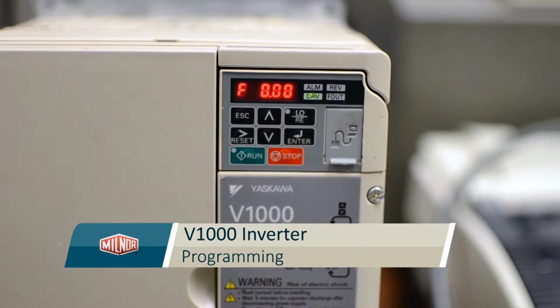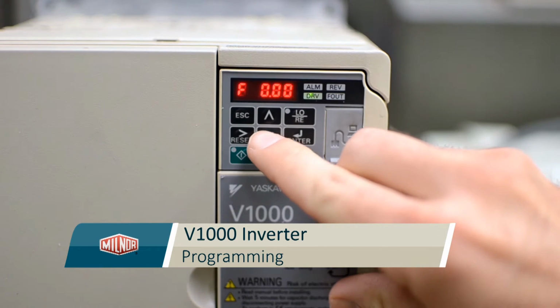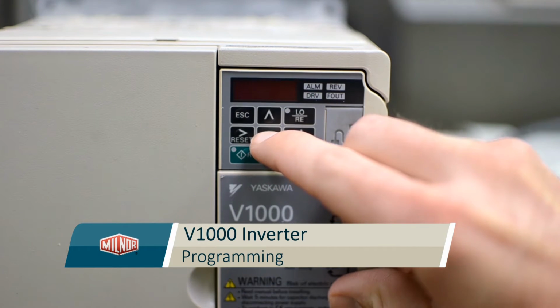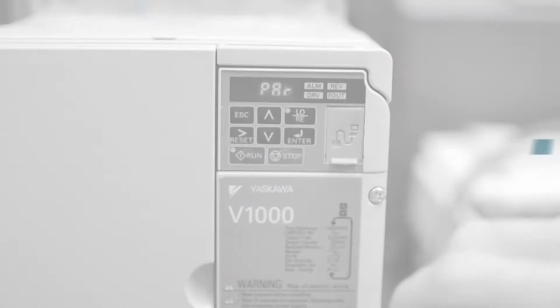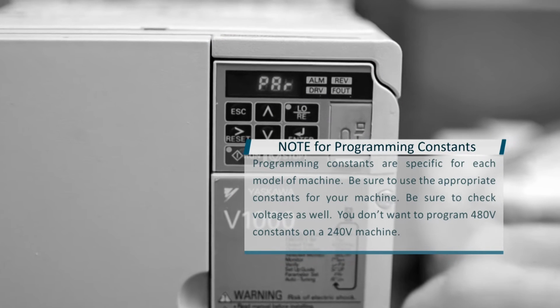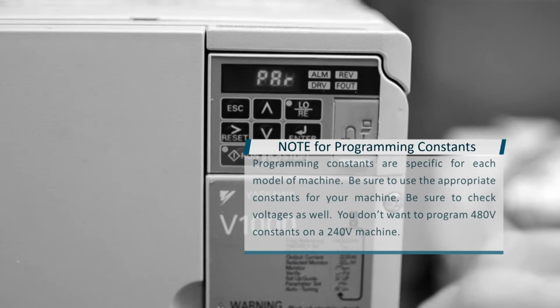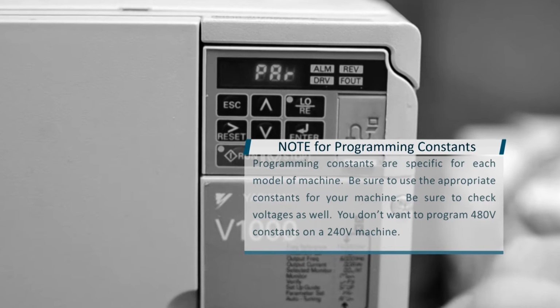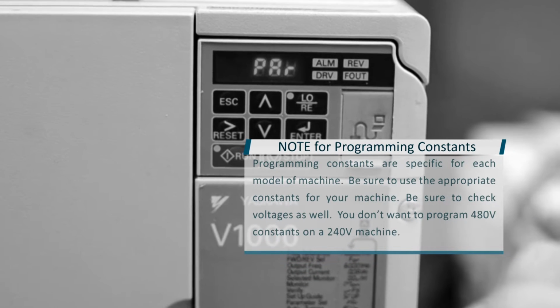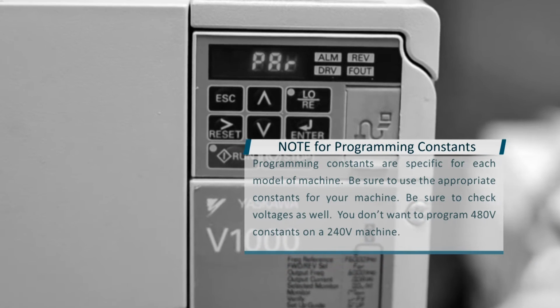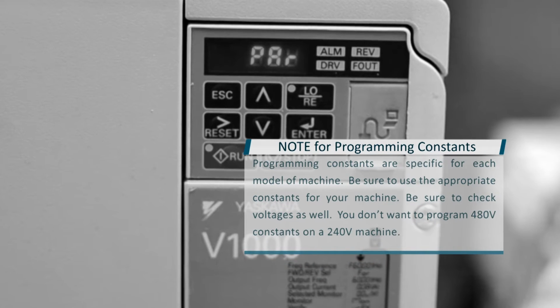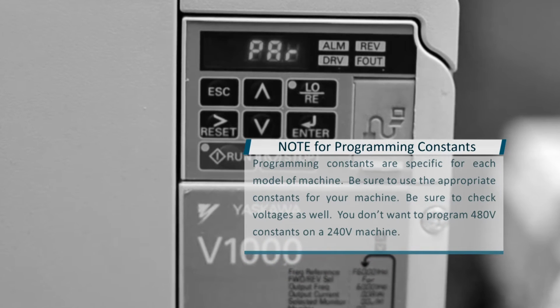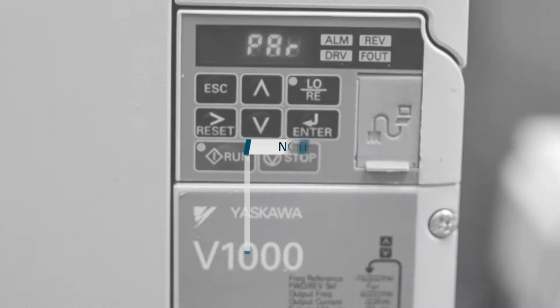Today we're going to take a look at programming the V1000 inverter. Press the down arrow twice until you get to the parameter menu. Note that programming constants are specific for each model of machine. Be sure to use the appropriate constants for your machine and be sure to check voltages as well. We don't want to program a 480 volt inverter with 240 volt constants.